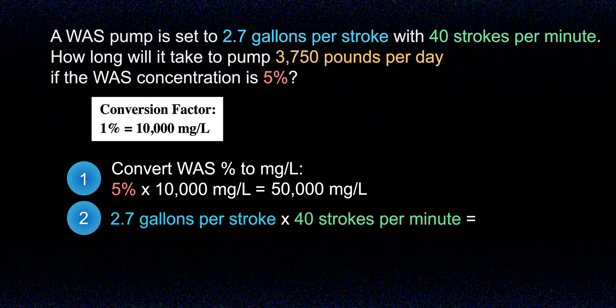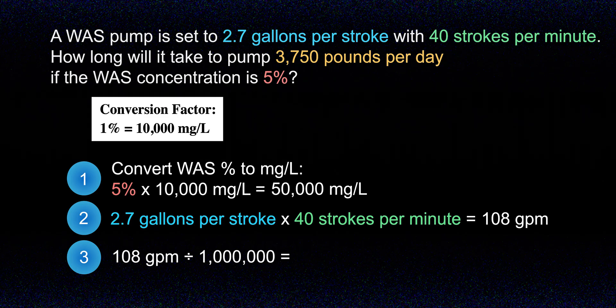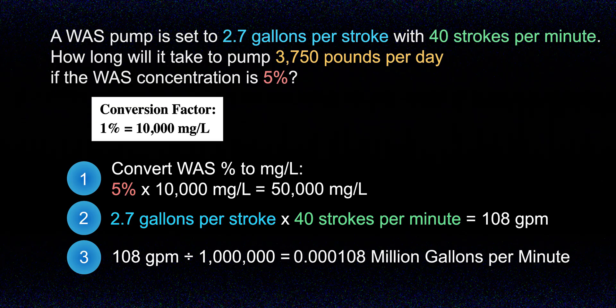For the second step, I'm going to calculate the pumping rate. I solve for this by using the 2.7 gallons per stroke multiplied by 40 strokes per minute, which gives us 108 gallons per minute. For the third step, I want to convert that pumping rate to million gallons per minute so we can use it in a loading rate formula. So let's take our 108 gallons per minute and divide that by 1 million, which equals 0.000108 million gallons per minute.